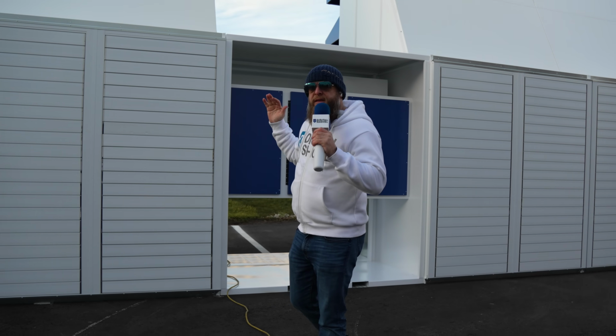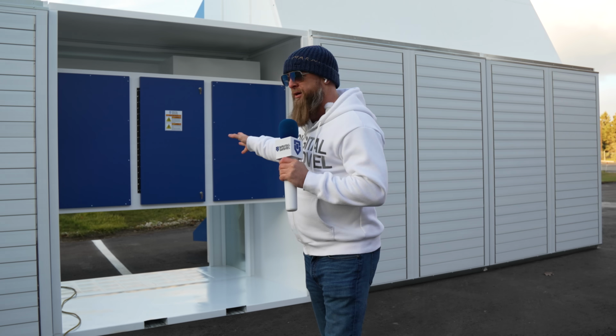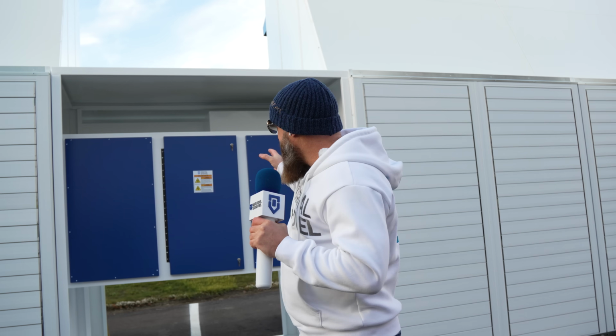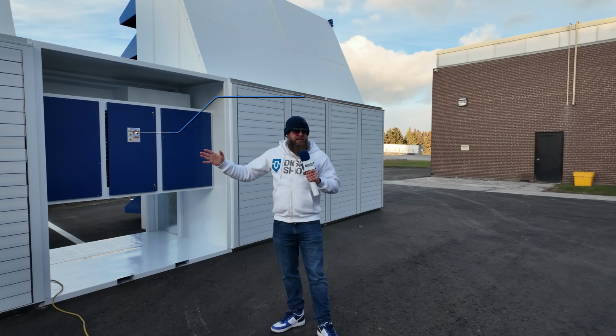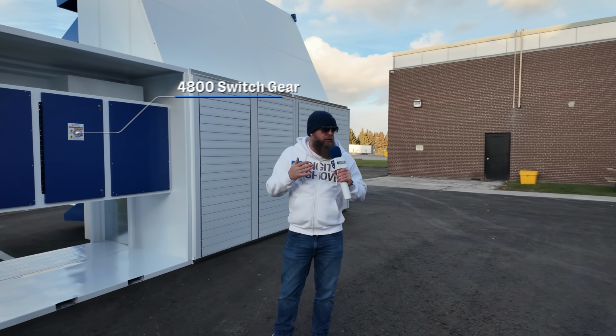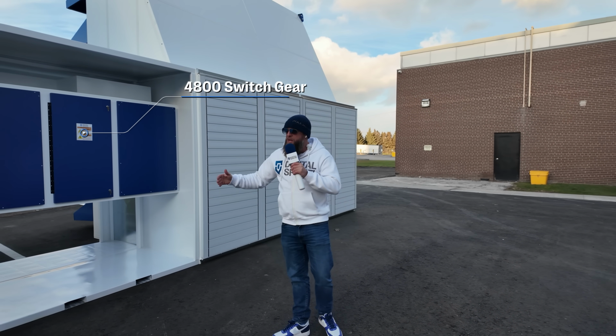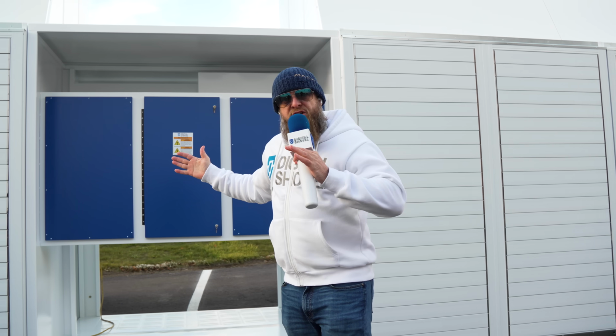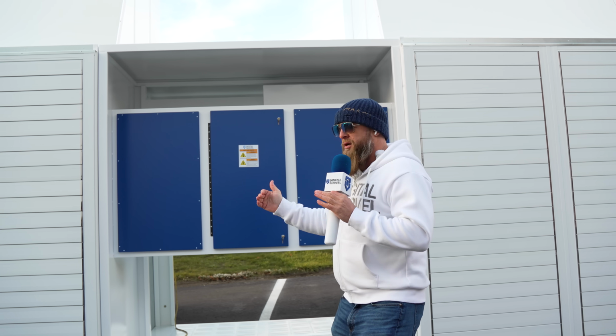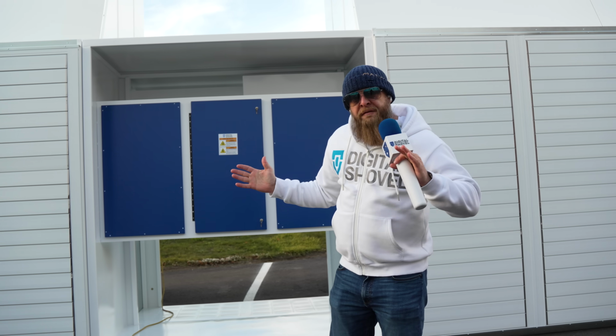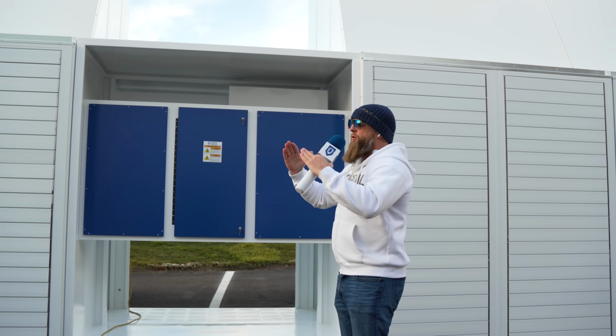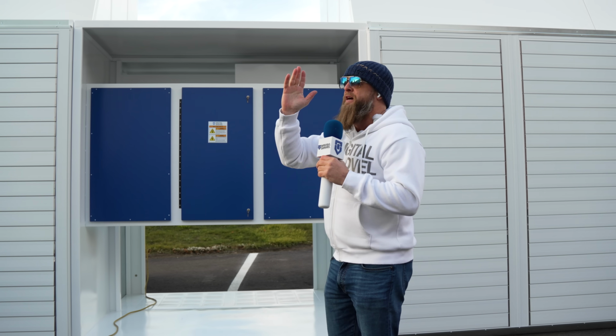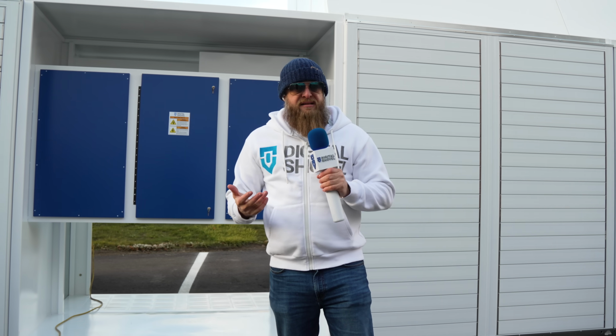So on the back within the pods, we've got our 4,800 amp switchgear. So from here, we can turn off our individual sections within the pod, and your transformers are going to connect to this main section. The way these are set up, you can actually have 2 units. So I could have 1 unit here, and I could have another string over here facing each other with the louvers pointing upwards, forcing that hot air up, and also helping to contain the sound.